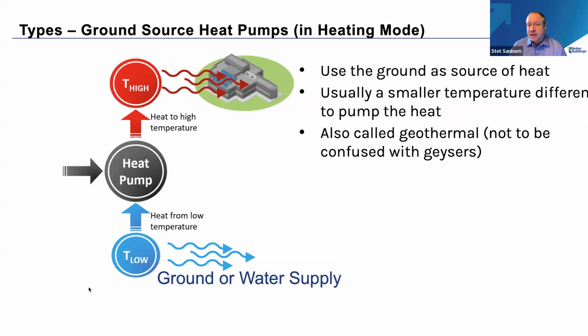Now, you'll also hear words such as ground source heat pump, geothermal heat pump, water source heat pump. Those are all types of heat pumps that, instead of using the outside air as a source or sink for heat, use some sort of groundwater supply or interconnection with the ground. Geothermal heat pumps are different from geothermal power plants. In a ground source heat pump, we have a heat exchanger that's buried in the ground. You'll see those U-tubes buried in bores spaced across your site. We push either hot or cold fluid into that bore field to exchange heat with the ground, extracting heat from the ground or pushing heat to the ground, and we use that as a means to heat or cool our building.